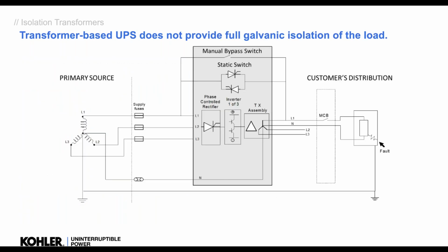So what we do get a lot of confusion around is that many people think an old traditional transformer-based UPS, because it's got a transformer on it, has this galvanic isolation of the load. It creates a new neutral earth, but it doesn't. So when we look inside a transformer-based UPS, we have a rectifier, inverter, a transformer here, and the output transformer star point is connected to the input neutral of the UPS, not to earth, because we're using this neutral to reference the output and we're referencing it with the bypass. Okay, so we cannot just connect this to earth, because therefore we would have a connection to earth at the source and we'd have a connection in the UPS to sources, but we cannot do that.